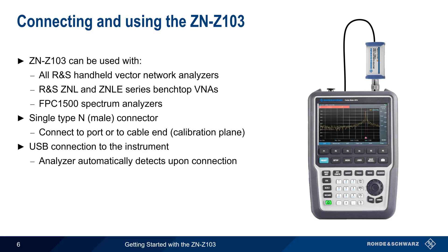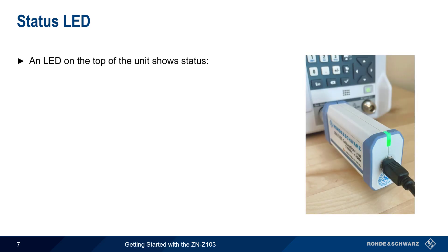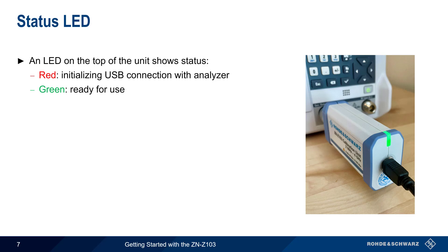Using the ZN-Z103 is very easy. Simply follow the instrument-specific instructions or menu prompts to start the calibration process. This process then runs without additional user input or intervention, and the complete calibration process normally requires less than 10 seconds. The status of the ZN-Z103 is reported by means of a status LED on the top of the unit. The color of this LED indicates the unit's state. The LED will be red while the unit is initializing its USB connection with the analyzer, and green when the unit is ready for use.